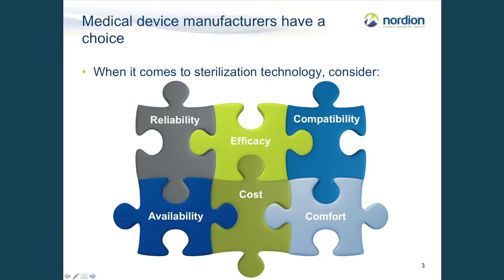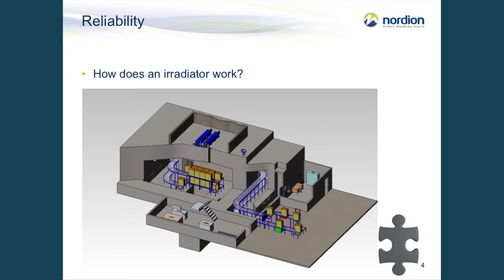To understand reliability, we first need to understand how a gamma irradiator works. The process begins with cartons or boxes of medical devices in their final sterile barrier system. The boxes are loaded into totes or carriers that are conveyed into a shielded room where they're exposed to a source of radiation. In this case, a rack filled with cobalt-60 pencils. Radiation penetrates the boxes. The amount of radiation is measured in dose, and the magnitude and distribution of dose in the product depends on the design of the irradiator, the amount of cobalt in the rack, and the time of exposure, so the time the product spends in the irradiation chamber.